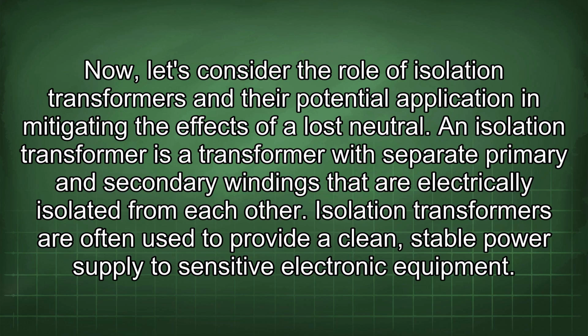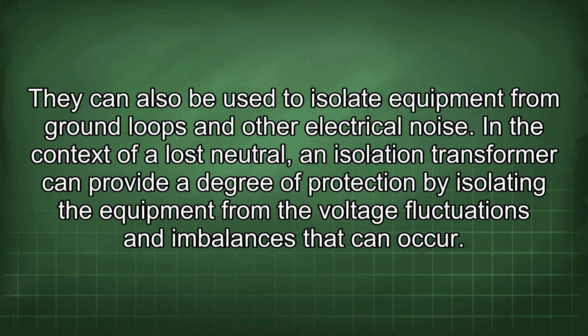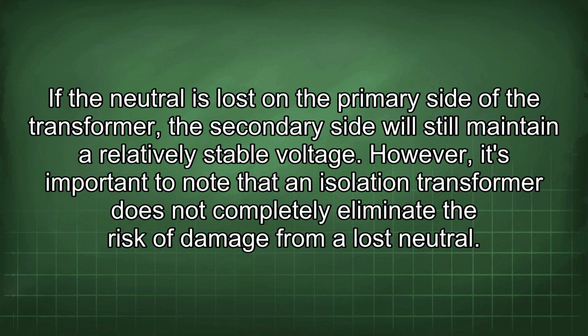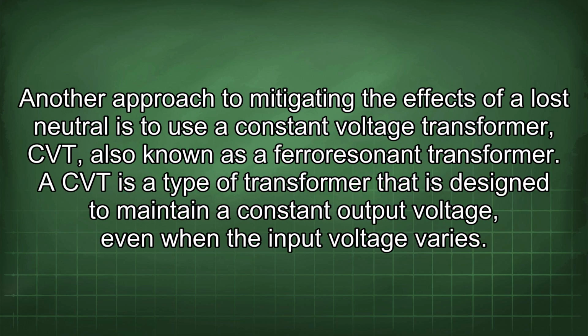Now let's consider the role of isolation transformers and their potential application in mitigating the effects of a lost neutral. An isolation transformer is a transformer with separate primary and secondary windings that are electrically isolated from each other. Isolation transformers are often used to provide a clean, stable power supply to sensitive electronic equipment. They can also be used to isolate equipment from ground loops and other electrical noise. In the context of a lost neutral, an isolation transformer can provide a degree of protection by isolating the equipment from the voltage fluctuations and imbalances that can occur.